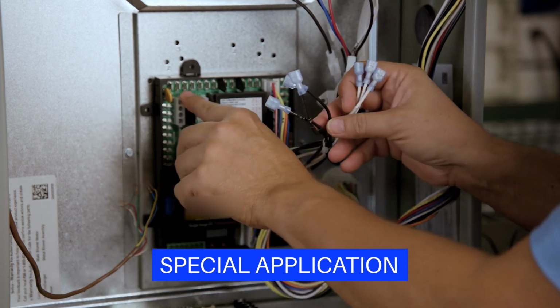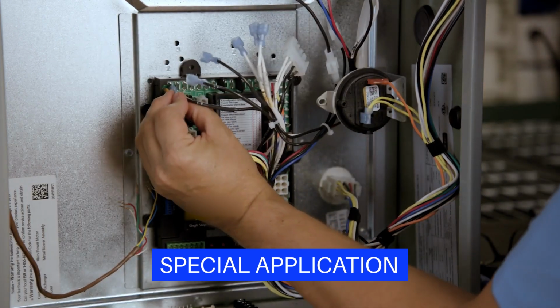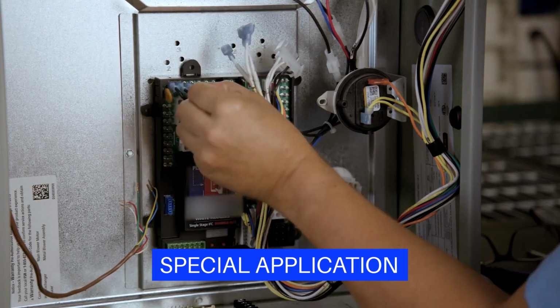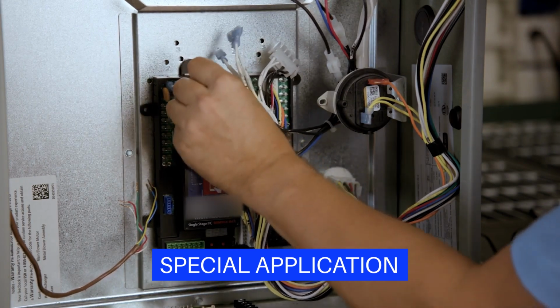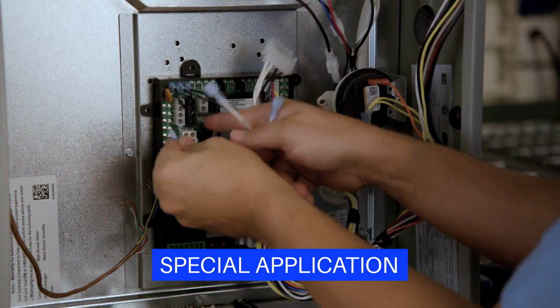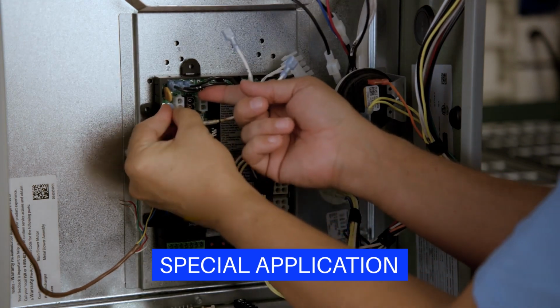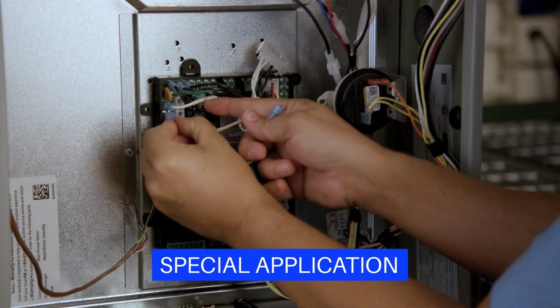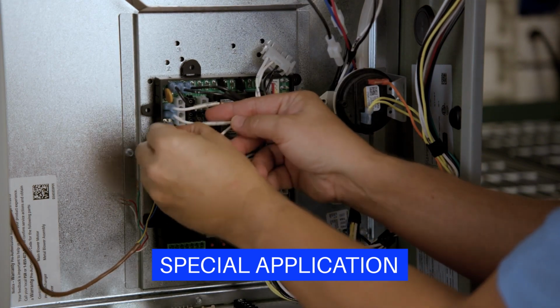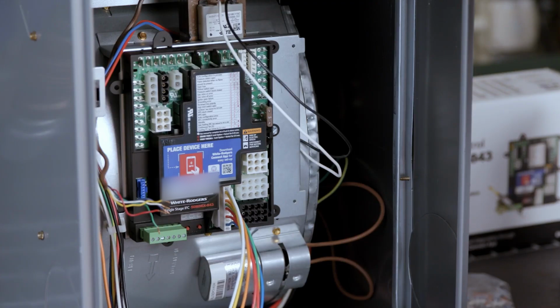The three 120-volt line wires can be connected to the line H, transformer H, and CIRC-H in any order, and the three neutral wires to the line N, transformer N, and neutral 1 terminals. For most applications, connect the individual wires to the new control board.